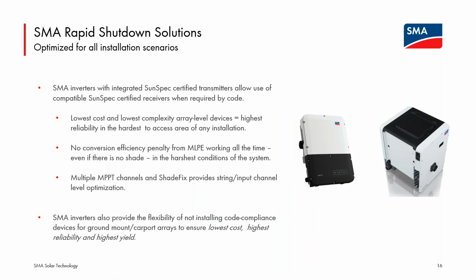That works into a rapid shutdown discussion in the US, in that we do often require in the United States, for rapid shutdown code compliance, some devices touching each and every module. But we at SMA advocate the use of simple code compliance devices that are not doing any power conditioning. So devices that are fairly simple, higher reliability, and are also not operating all the time, to avoid that continuous DC loss. Now in the US, the 2017 and 2020 code books, adopted at various times by different states, are requiring this, in essence, module level shutdown. And that has been the rule anytime a state adopts code from 2017 on.